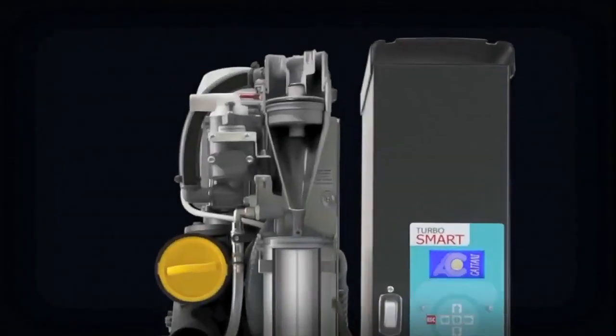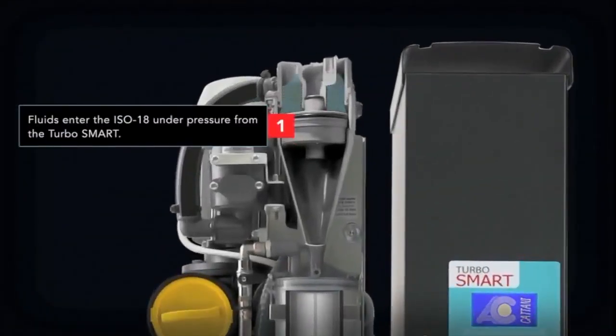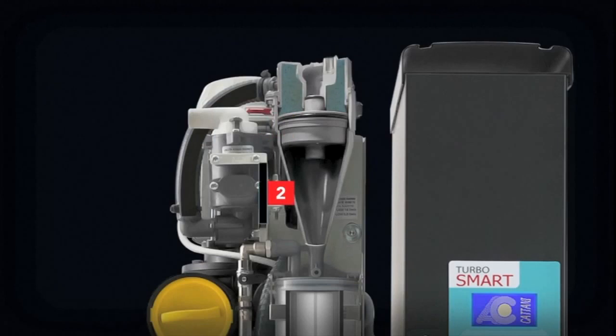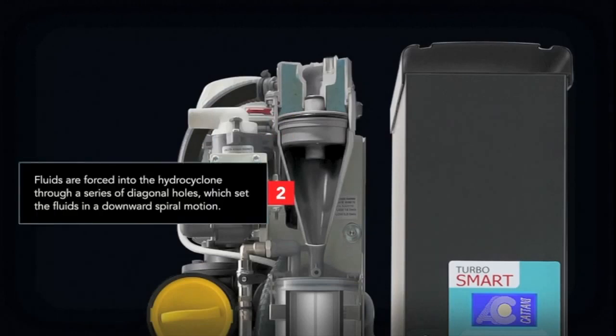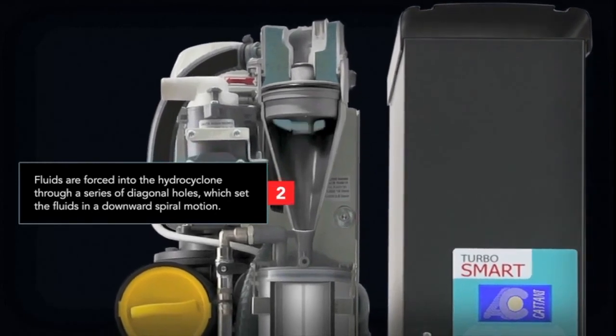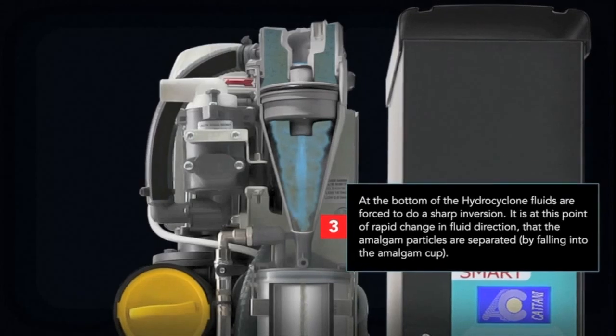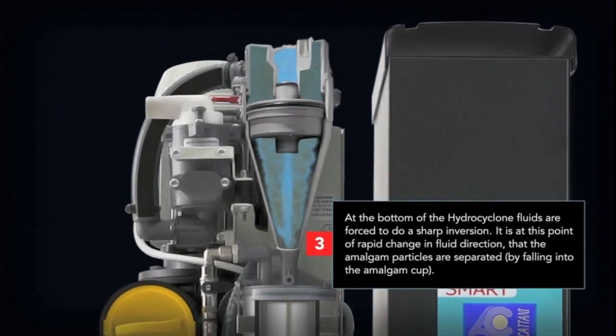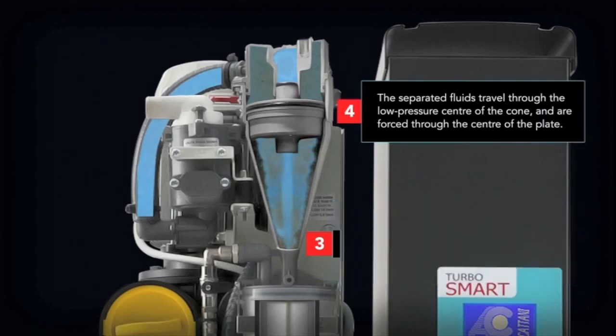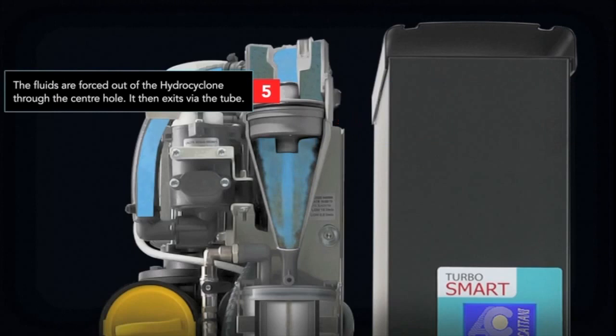How does our amalgam separator work? Firstly, fluids enter the ISO 18 amalgam separator under pressure from the TurboSmart. These fluids are then forced down into the hydrocyclone through a series of diagonal holes, which push the fluids down in a spiral motion. When these fluids reach the base, they are then forced back up through the hydrocyclone. It is at this point of rapid change in fluid direction that the amalgam particles are separated and extracted down into the amalgam pot. The separated fluids travel up through the low pressure centre of the cone and are forced through the centre of the plate. The fluids are then forced out of the hydrocyclone through a centre hole, which then exit via a tube.